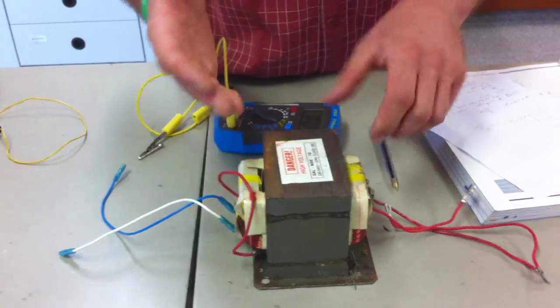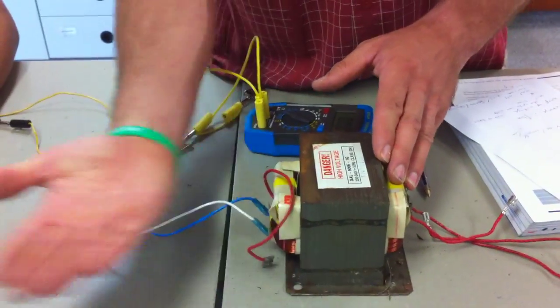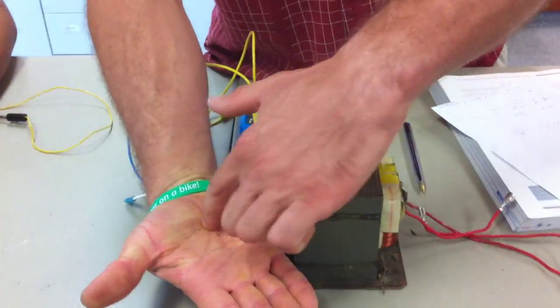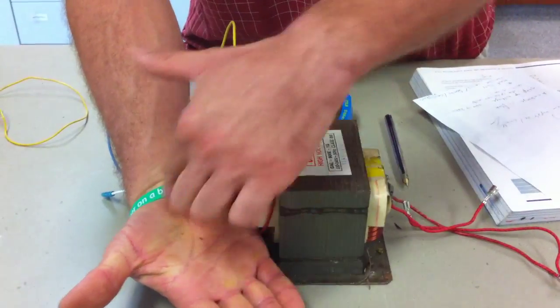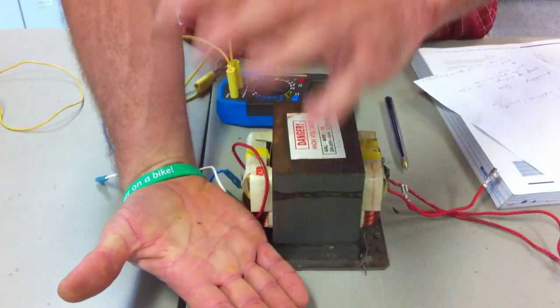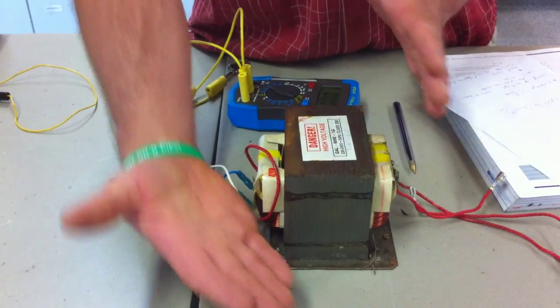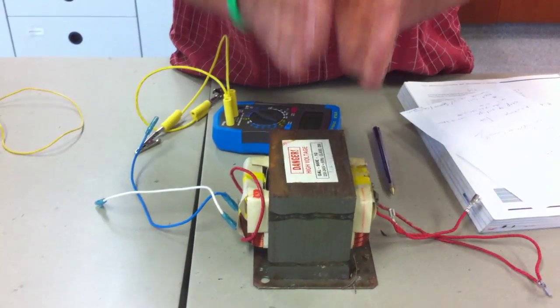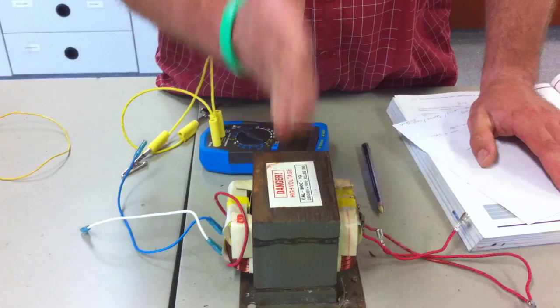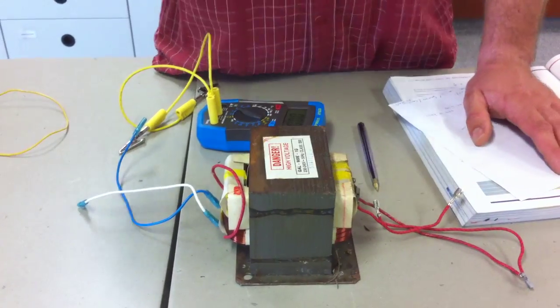If the lamination was this way instead, then the eddy currents would run quite happily and it wouldn't work. So the aim is to minimise the wastage of heat from eddy currents, and that's done by lamination.